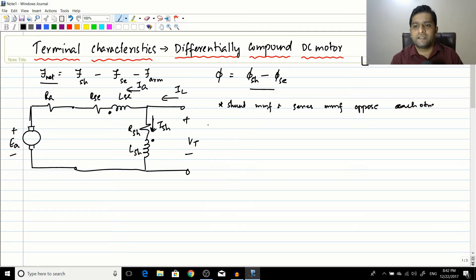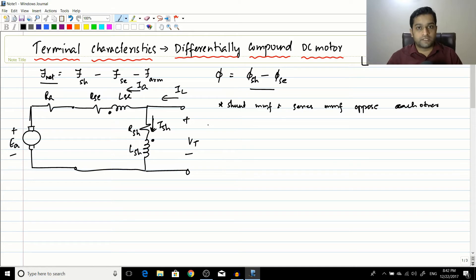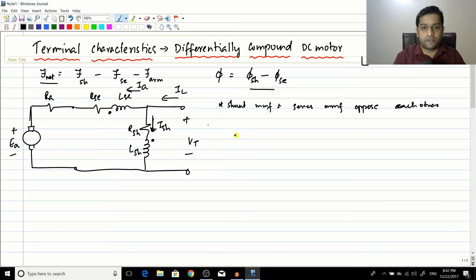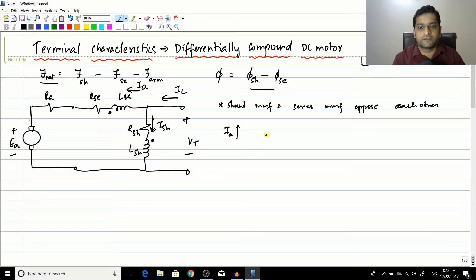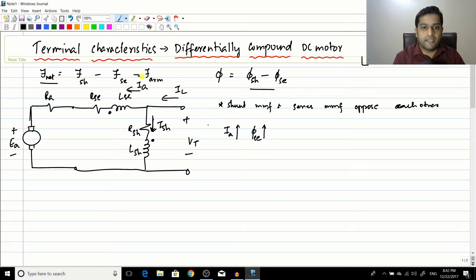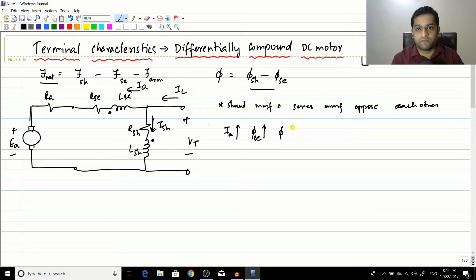Let us see what happens if we load the motor. Assume the motor is running and we load it. As Ia increases, the series flux increases. The shunt flux does not increase — only the series flux increases. So the net flux falls down, which means omega (speed) will increase.